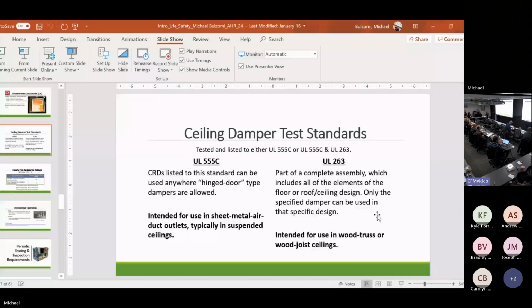if you are approving multifamily wood truss projects, pull the UL listings the architect gave you. And if you don't have the architect's information on what the assemblies are, you can't approve the damper because you don't know what's allowed. The worst thing that happens all the time: buildings are being built, everything's being ordered, the architect finally gives you the assembly number, you go to the UL directory and guess what? It's never been tested and approved for use with a damper. What do you do then?